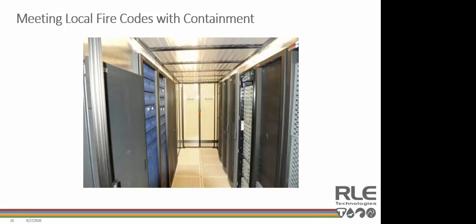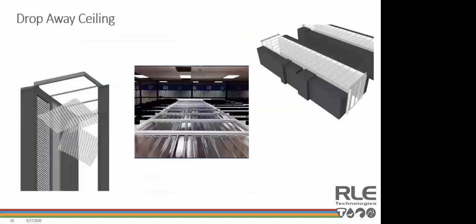Typically, when you contain a space in a data center, you're really, in effect, creating another room or plenum. And should there ever be a fire event, the fire suppression systems need to be able to access this newly contained space. Obviously, one way to do this would be to outfit each contained space with its own fire suppression system, like adding a new sprinkler head, but that would become extremely expensive extremely quickly. And we have designs that help, with containment solutions, work around those types of scenarios. In addition to making sure the contained spaces have access to fire suppression systems, the materials themselves often need to meet certain UL flame rating and/or NFPA, or National Fire Protection Association, specifications. To address this, we've come up with some unique solutions, which I'll talk about in the next few slides.